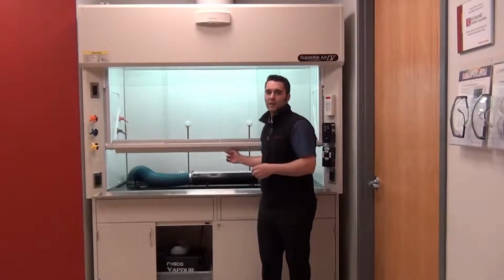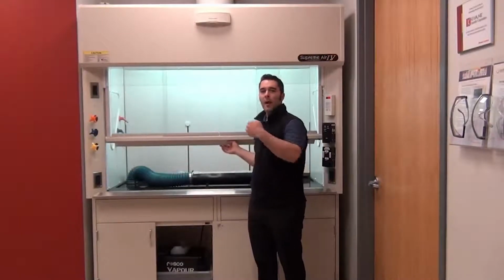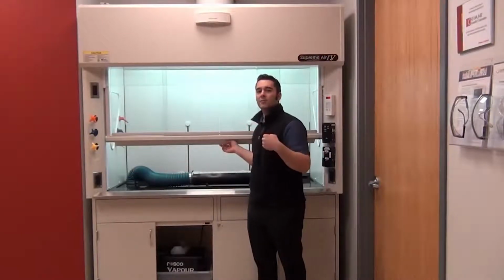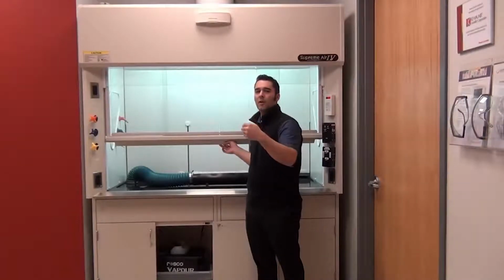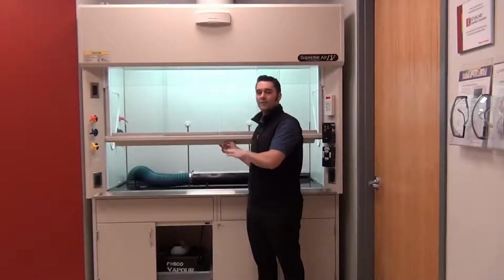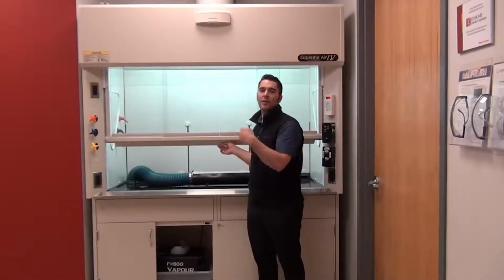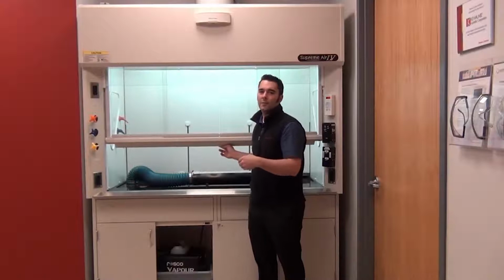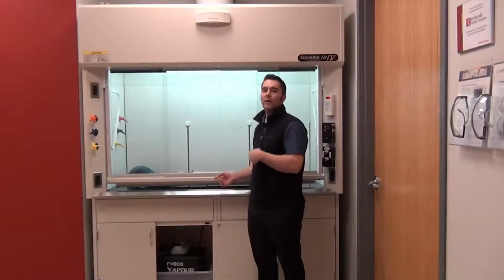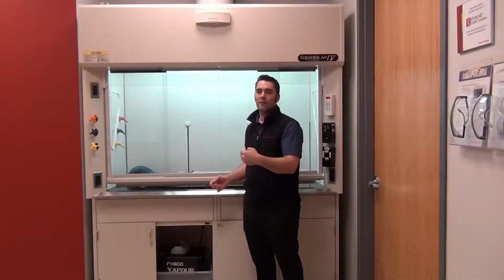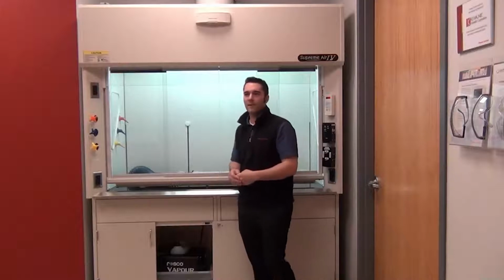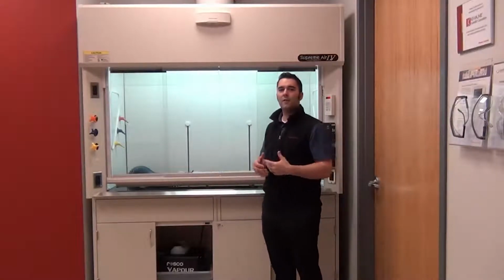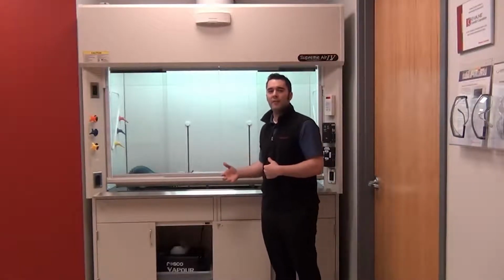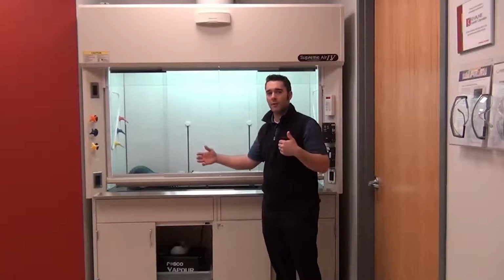So as fast as I can move this valve up and down, my actuator is tracking my sash movement within 1 second. Also, my cone inside of my valve is automatically adjusting to the pressure changes in the ductwork. So as this valve sits in its steady state, I don't have it hunting all the time to try to maintain a set point. It will go to its set point and it will stay there and give you an accurate airflow throughout the course of the day. It also guarantees that we have plus or minus 5% accuracy through all of our set points.